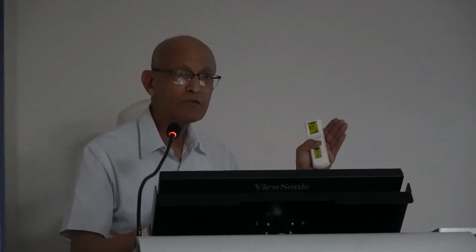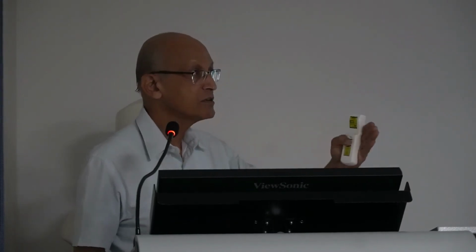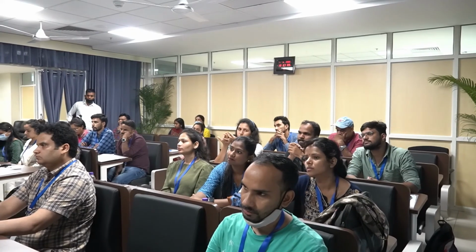That typically we use a mercury lamp here because it provides a very strong light beam and entire wavelength from ultraviolet to infrared. All the wavelengths are part of this, and so this light comes through a series of lenses and a series of filters that can be built in here to the excitation filter, which selects a particular wavelength that will be passed on to the fluorochrome there, and then both these green and the red fluorescent light travel through. Dichroic mirror lets both of them pass through, but now we have a red filter here which will not allow green, allow only the red to pass through, and that's how we see the fluorescence.